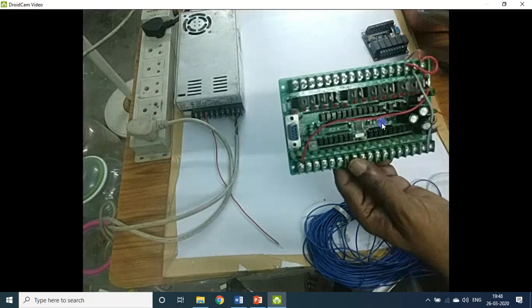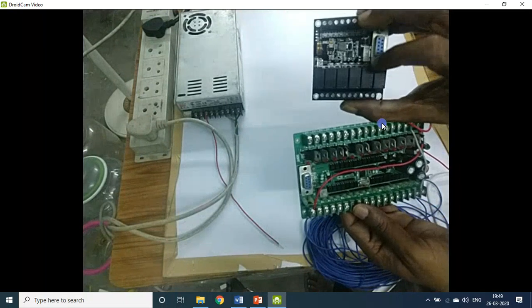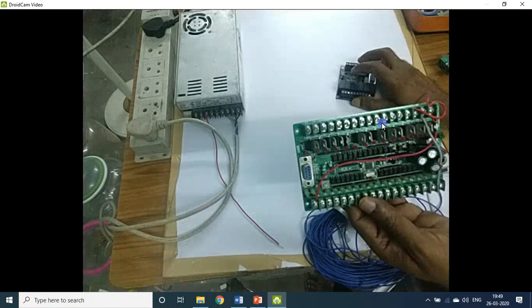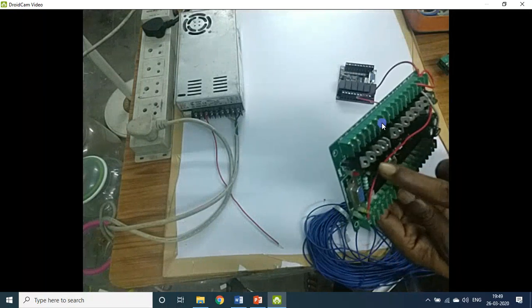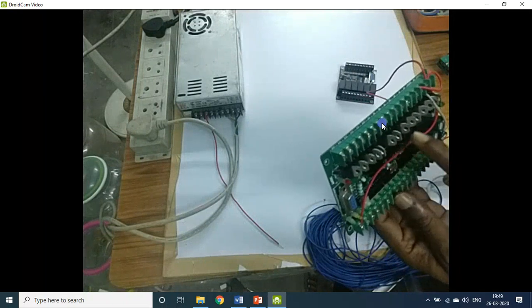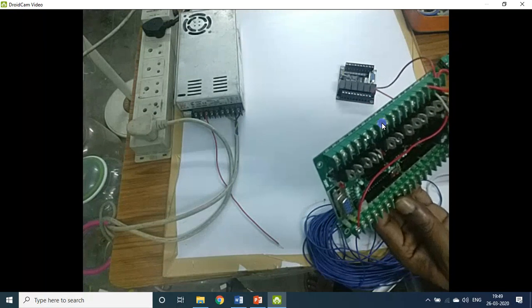This is the transistor type board. Here, you won't have the relay cubes — these are transistors: 1 through 14. So it has 14 outputs. This side reads '30MT' — 30 means the sum of inputs and outputs equals 30, so 14 outputs plus 16 inputs. 'T' stands for transistor, not relay type.